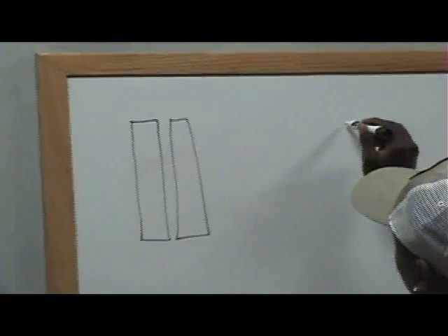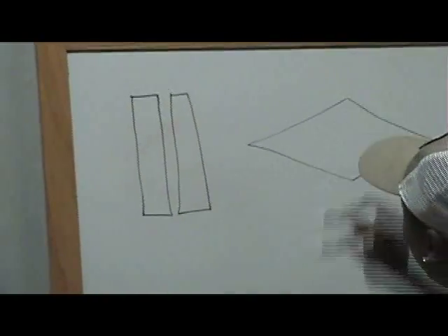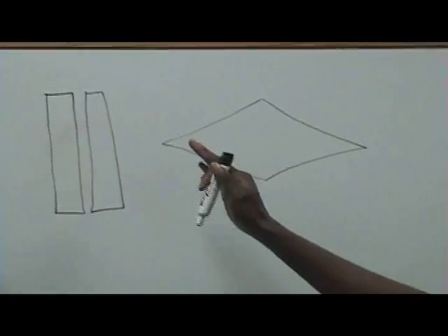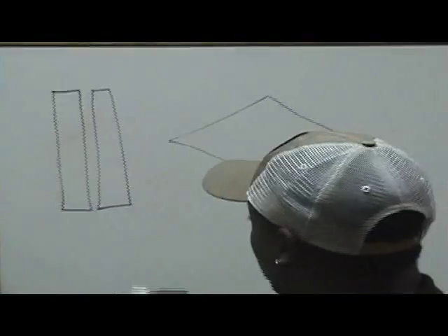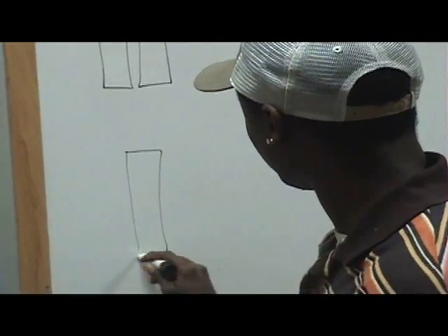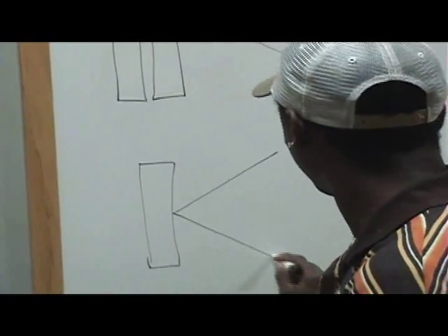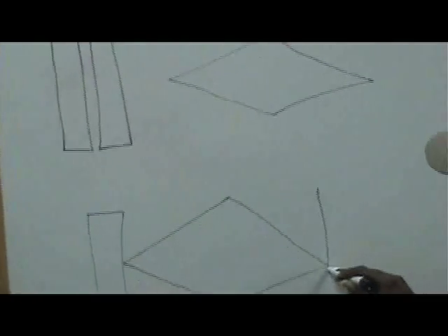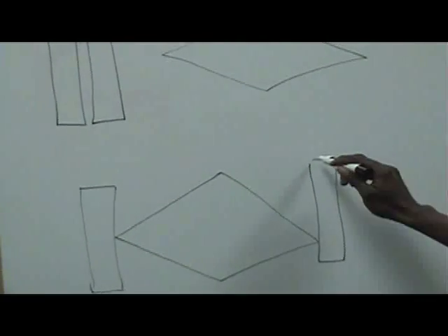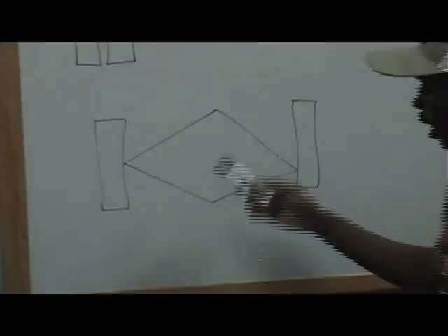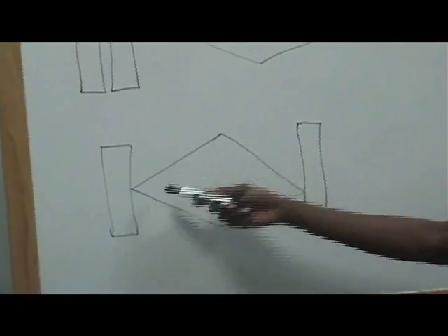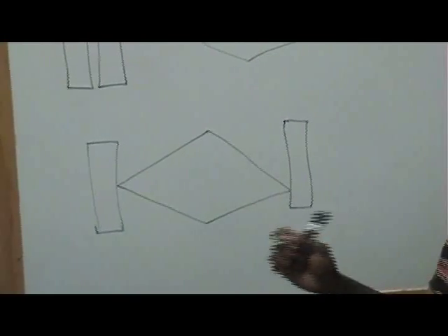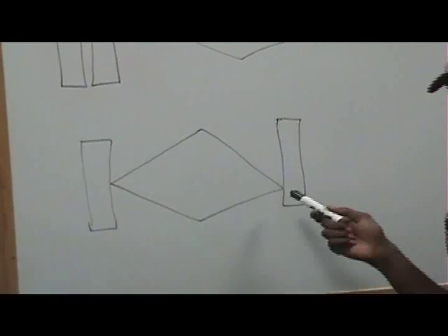After we have the lines like this, the microhardness tester is going to make an indentation mark like so. This right here is the new indentation mark. We're going to position the lines right next to the outermost portion of the indentation mark. So it's going to look like so. Okay, now with the right line, we're going to put that on the end of the other side of the new indentation mark. And so this should be our final product. After we have the lines on the left and the right outermost portion of the new indentation mark, we're going to use the filar adjuster to measure the length and distance across the new indentation.